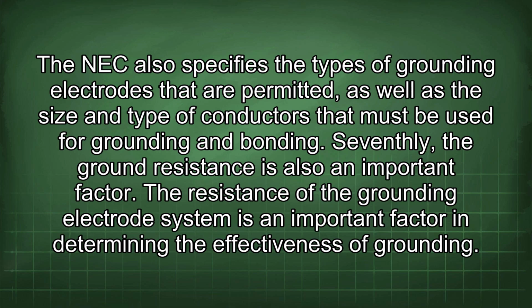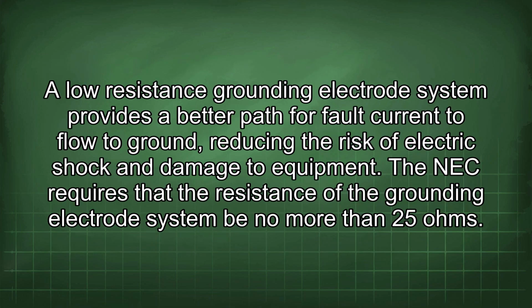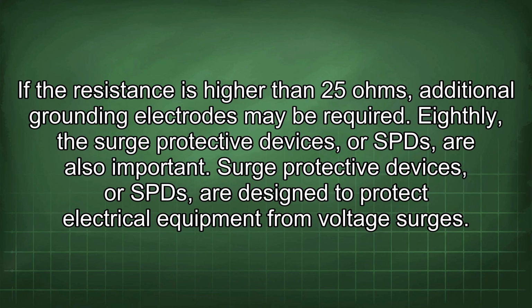Seventhly, the ground resistance is also an important factor. The resistance of the grounding electrode system is an important factor in determining the effectiveness of grounding. A low-resistance grounding electrode system provides a better path for fault current to flow to ground, reducing the risk of electric shock and damage to equipment. The NEC requires that the resistance of the grounding electrode system be no more than 25 ohms. If the resistance is higher than 25 ohms, additional grounding electrodes may be required.